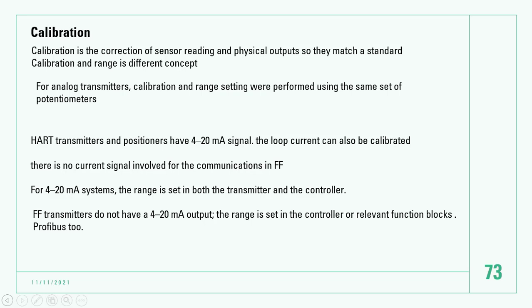if you use HART communication in a 4 to 20 mA system, if you set the range, it should be set in the transmitter and the controller. If you set the range in the transmitter, you also set it in the controller for the soft logics, the control logics. In Foundation Fieldbus, it is the AI block, analog input block, where you should set the calibration. Okay, FF transmitters don't have a 4 to 20 mA output. The range is set in the controller, just in the function block.